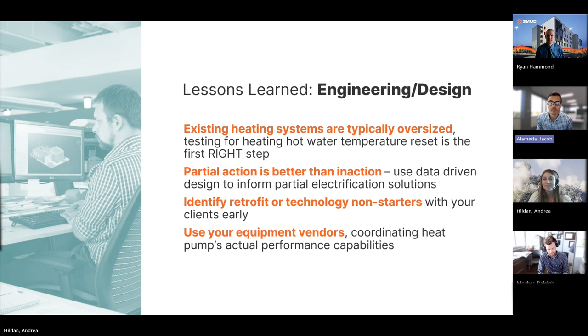And then the last one is use your equipment vendors. This heat pump technology is advancing really quickly, and every heat pump has different system requirements in the way it operates: minimum flows, minimum pressures, how it responds to your pumps, whether it wants to be variable speed primary or primary-secondary pumping scheme. So just talk with your vendors and really build a close relationship with them so they have a lot of say in how the system's going together.